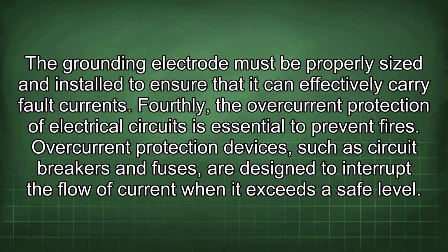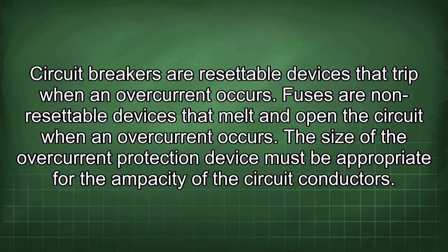Fourthly, the overcurrent protection of electrical circuits is essential to prevent fires. Overcurrent protection devices, such as circuit breakers and fuses, are designed to interrupt the flow of current when it exceeds a safe level. Circuit breakers are resettable devices that trip when an overcurrent occurs. Fuses are non-resettable devices that melt and open the circuit when an overcurrent occurs. The size of the overcurrent protection device must be appropriate for the ampacity of the circuit conductors.